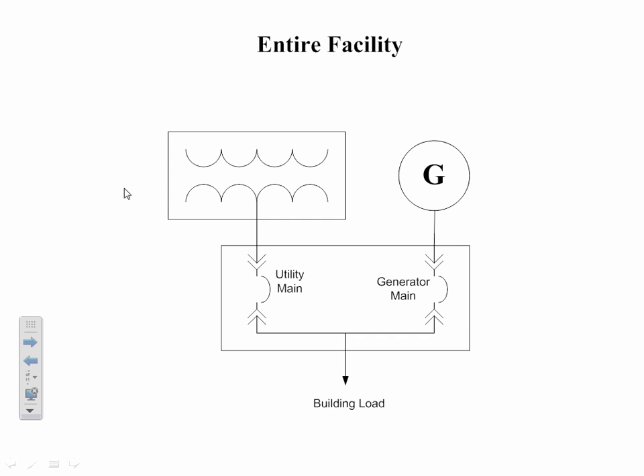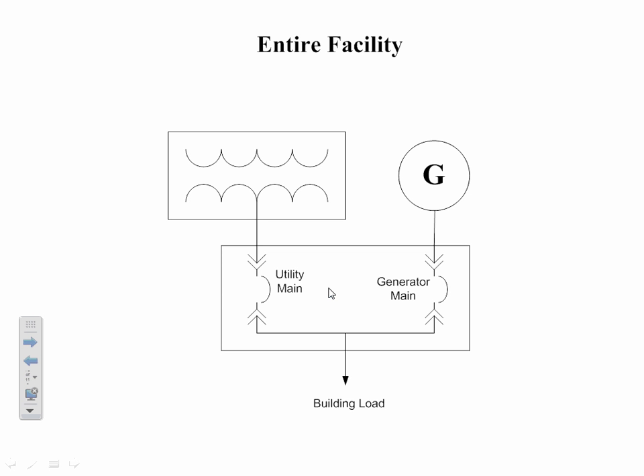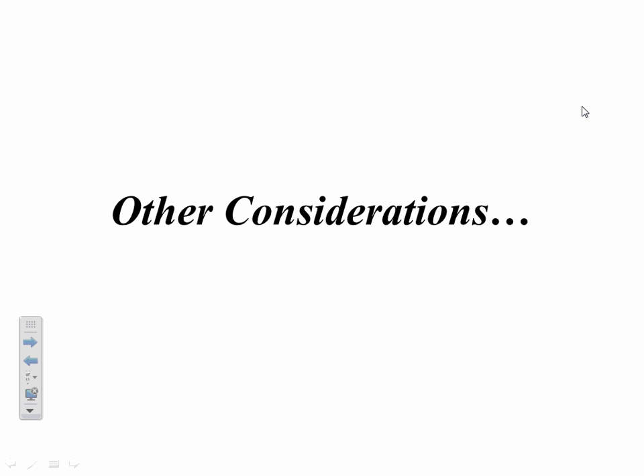Reverse is true when utility comes back. Sensors see it, tell the generator to synchronize. The generator control then is in sync with the utility. It closes the utility main. Signal is then given to do the shutdown sequence for the generator, the cool down, and so on. Again, opening that breaker, cooling the generator down, shutting it down. Load doesn't know anything happened. That's the entire facility. It's a lot cleaner for others, for outside.